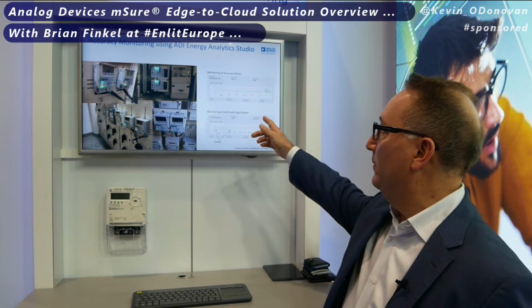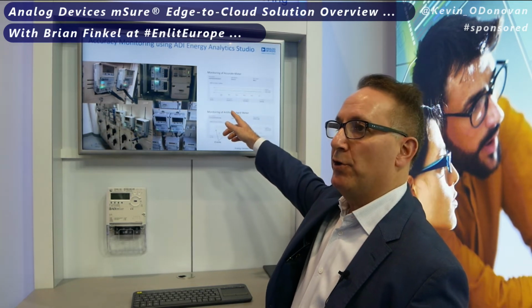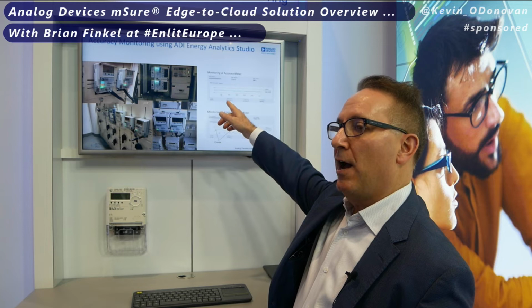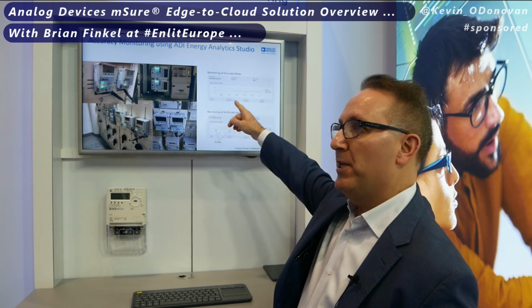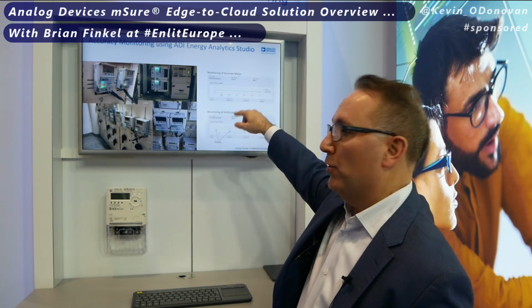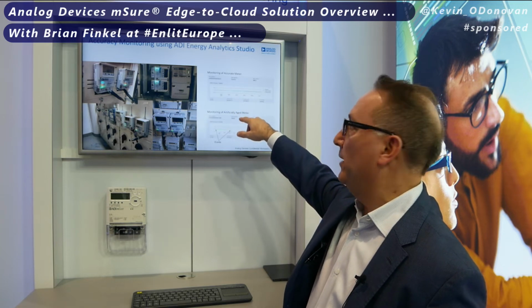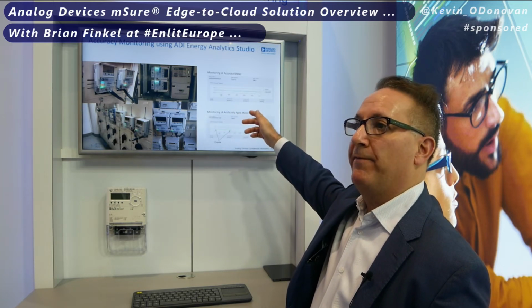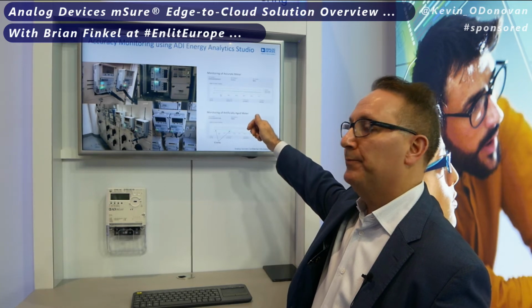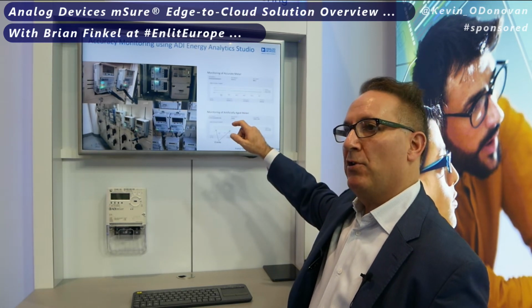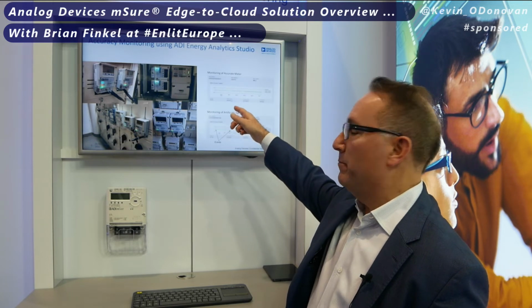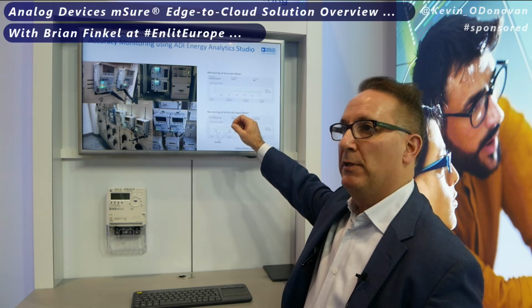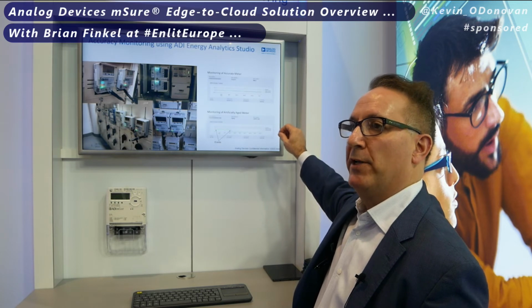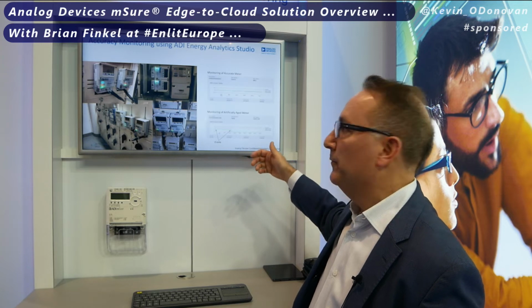If you look on the right, you see a snapshot of our user interface. The green line represents the accuracy of the meter over time, and the vertical axis represents accuracy, with the limits being 0.5 to represent a class 0.5 meter. You can see that when this meter was installed, it started measuring accurately at 0, and it maintained its accuracy over a few months. That's exactly the result you'd expect to get with an accurate meter. So here we're just testing out the system to make sure it works.